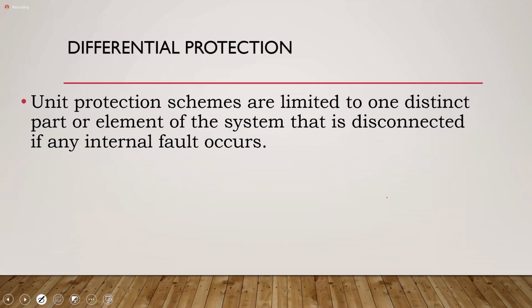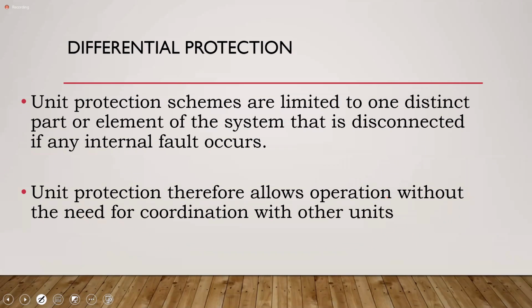Differential protection. Now, we mentioned last week about unit protection, that it looks at a distinct part or component or element within the system, and it will disconnect it for any internal fault. And so there doesn't need to be any what we call coordination. In other words, as part of your protection system, and this is something that we'll look at in more detail, there is coordination, meaning there is consultation with other parts of the network to ensure that our main objective is achieved, which is to keep as many customers connected as possible. All right. So with unit protection, you don't have to do that coordination. So if there's a fault on the equipment that is protected, you just separate.